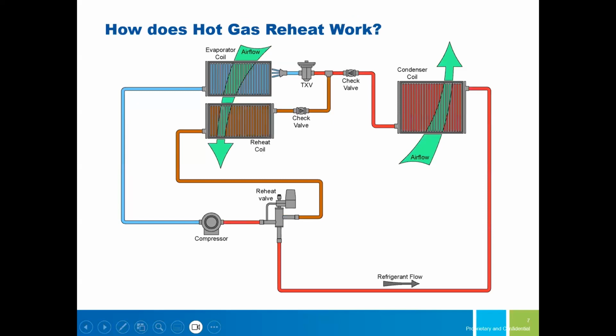So this is that pretty diagram, just to show you that reheat coil and what takes place. You've got the hot gas coming off the compressor. You've got a reheat valve there, based on the circumstances within the system about whether reheat's needed. And then for a package unit, there are internal controls looking at all the temperatures within the system to figure out whether it needs to be running reheat, cooling, or traditional heating mode. And then there's a check valve to keep any re-entrainment back in the system.